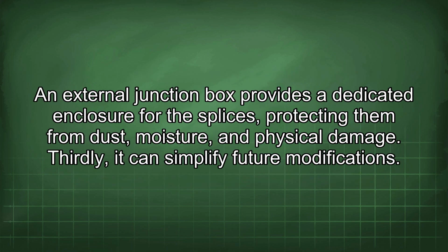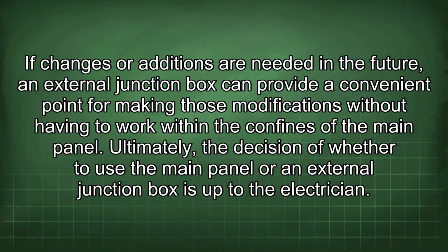Secondly, it can provide better protection for the splices. An external junction box provides a dedicated enclosure for the splices, protecting them from dust, moisture, and physical damage. Thirdly, it can simplify future modifications. If changes or additions are needed in the future, an external junction box can provide a convenient point for making those modifications without having to work within the confines of the main panel.